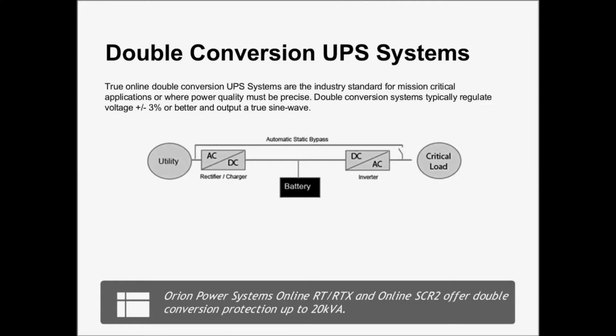The last design we're going to talk about is the double conversion UPS. This is the most robust design, and gives you by far the best power quality. Essentially, the reason these systems are called double conversion is they bring in the utility power, convert from AC power, or wall power, to DC or battery power, and then the battery is wired in parallel, and then it converts from DC power to AC power and powers the load. So essentially, it creates its own power with the inverter at all times. Because it's running off the inverter at all times, it has to output a true sine wave.